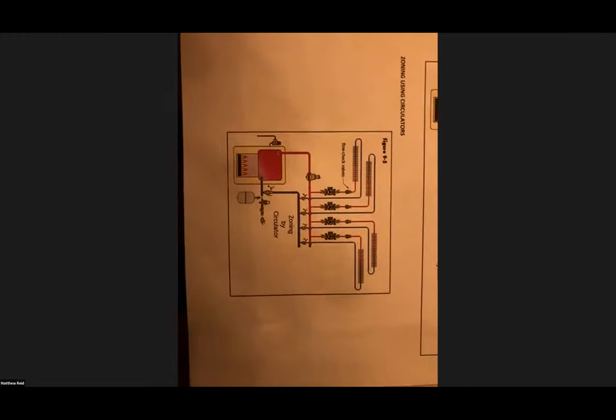Really cost effective, if you want. It doesn't involve the hydro separator, but again, not everyone can afford that. Maybe you don't have the budget for it, but you still need to get heat into the house. This can be an option for you, but I would still add a dirt separator somewhere in there. Again, if you don't put a filter in your furnace, then you don't need to use one in your boiler, but I guarantee you got one in your furnace though, don't you?